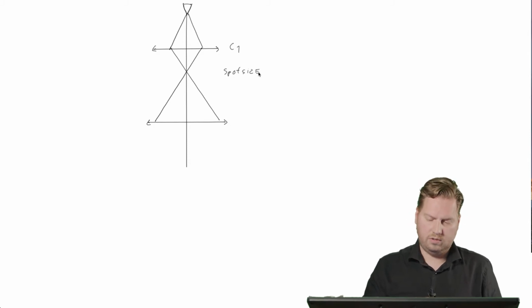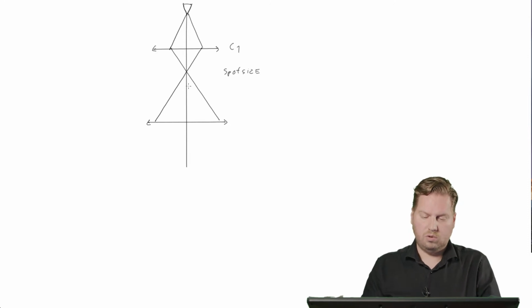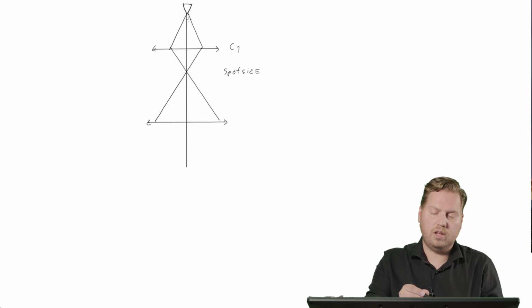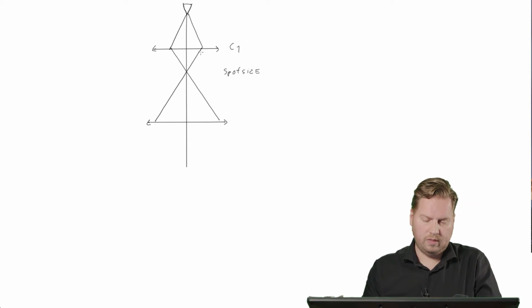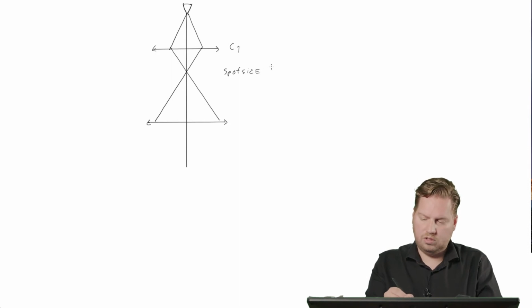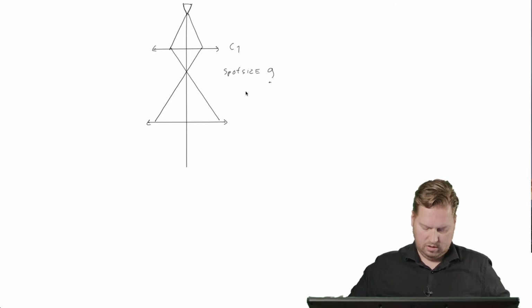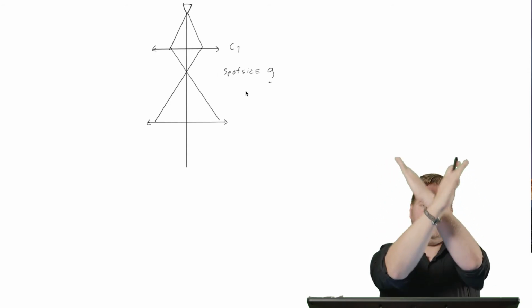And if you change your spot size, you can understand that this crossover, this focal point of that lens, moves up and down. So if we would have the same amount of light or the same angle of the electrons going into this first lens, and we change the spot size, for instance, to a weaker lens. Let's assume this is spot size 9. And we go to spot size 3. So we make the lens weaker. That means that if you look at my arms, the lens does this. And the crossover, which is the cross between two of my arms, goes down.